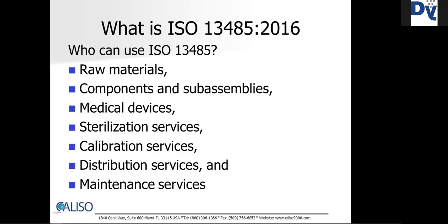It is not the intent of ISO 13485 to imply the need for uniformity to the structure of the standard. In ISO 13485, the following terms or phrases are used. When a requirement is qualified by the phrase as appropriate, it is deemed to be appropriate unless the organization can justify otherwise. When the term risk is used, the application of the term within ISO 13485 pertains to safety or performance requirements of the medical device or meeting applicable regulatory requirements.